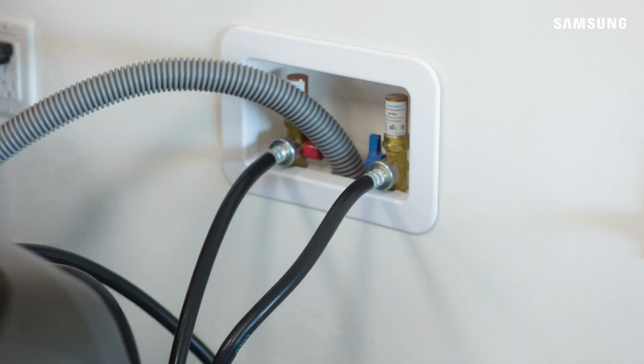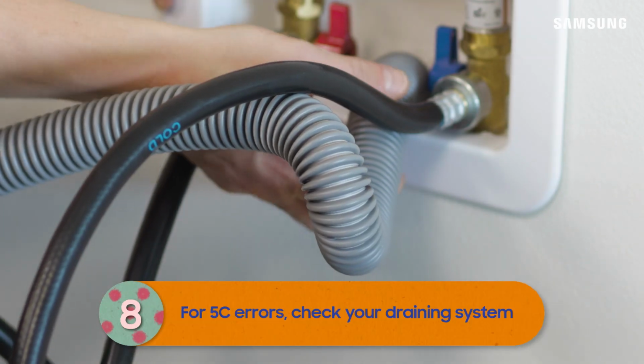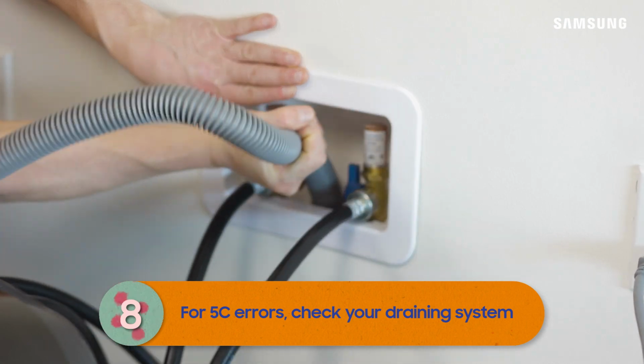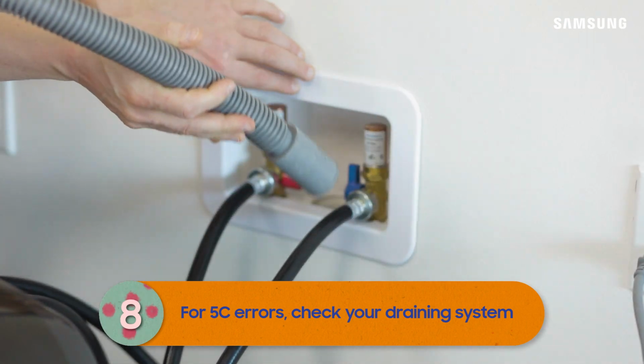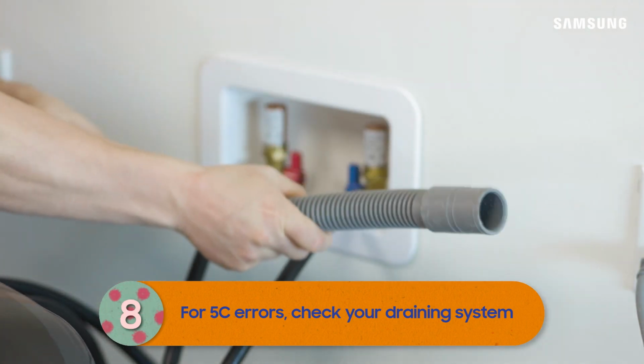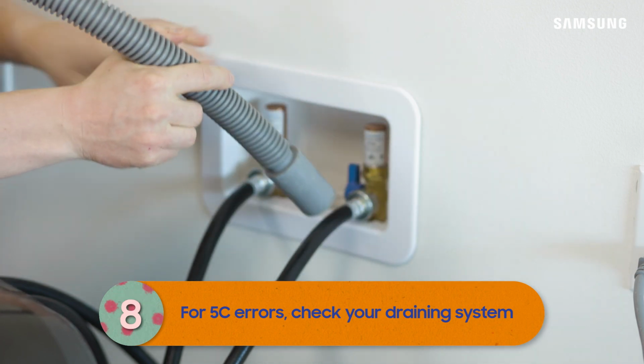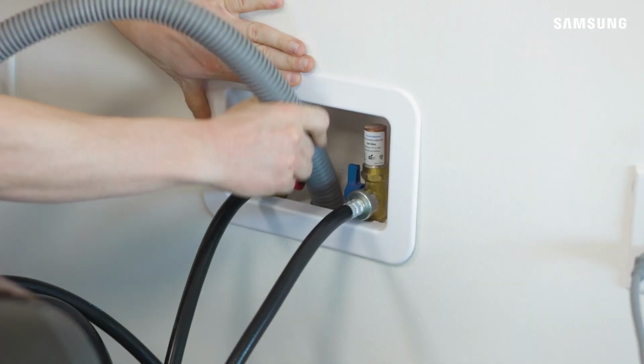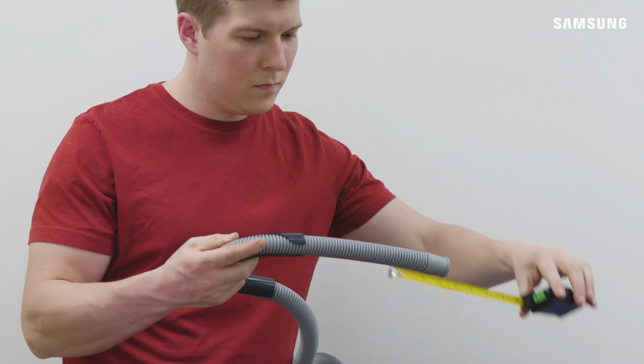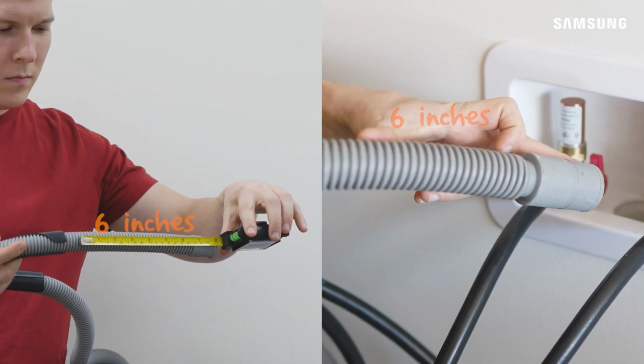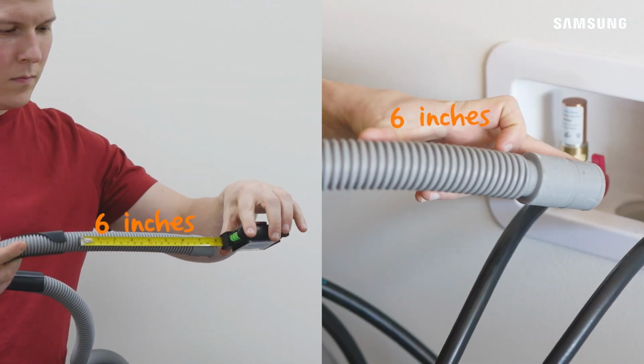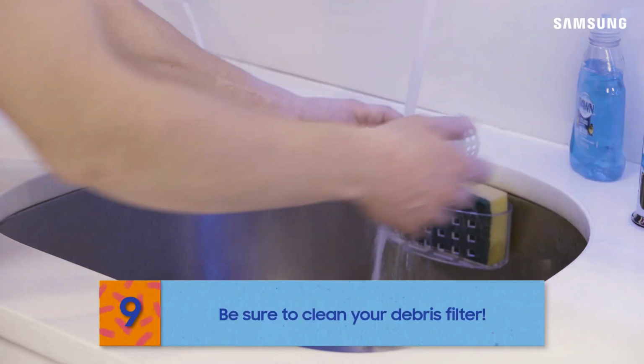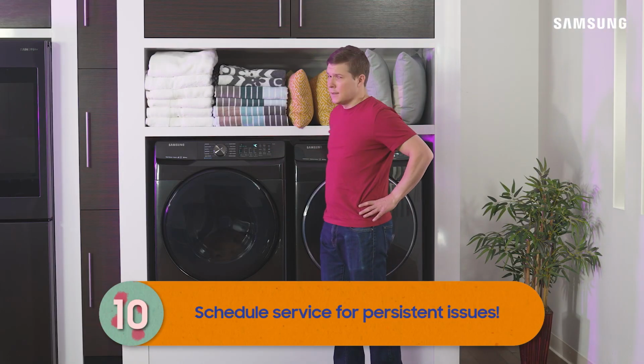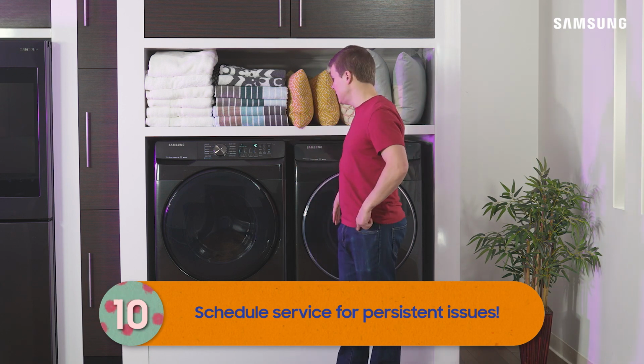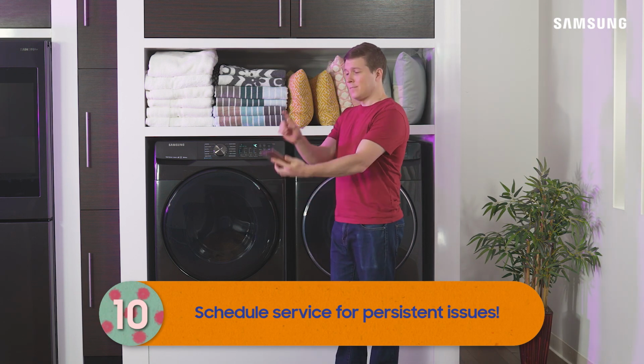A 5C or OC error code indicates that the drain pump isn't working as well as it should. Check the drain line for any kinks or foreign material, and make sure the drain pipe is installed according to the manual instructions, especially the part about being inserted no more or less than 6 inches into the home's drainage system. Remember to regularly clean your pump filter. If these checks don't help the issue, or if any other error code appears, it might be time to schedule service.